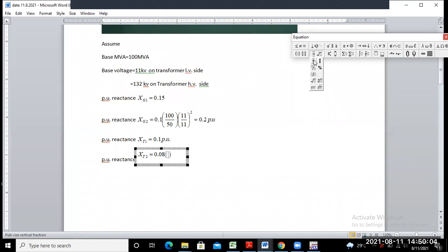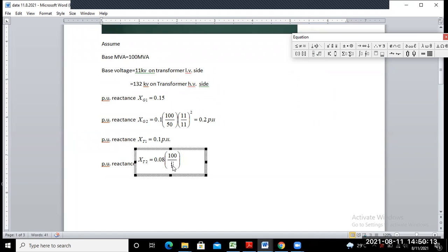Always keep in your mind this point. Then you just put simply on the formula. So MVA new is your 100. What is the MVA old here? Transformer 2, what is the MVA rating? 50 is it not. MVA old value is your 50. And kilovolt base old, how much? Kilovolt base old is equal to how much? 11 kilovolt. And again, MVA new, kilovolt base voltage new is your 11 kilovolt. So again 11, that is, this one is your whole square.